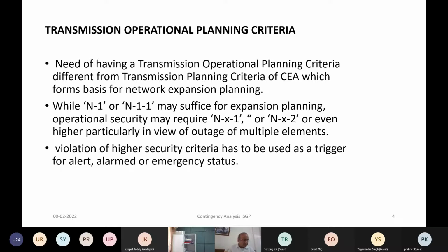Very often, though the planning envisages certain things, in practice the network gets modified because of unforeseen loads being fed or unforeseen conditions of load drawal. We very often hear in terms of grid discipline that a certain region has overdrawn as compared to the schedule. It happens in catering to, say, agricultural load or due to some environmental condition. Suddenly one region may start drawing more power than what it is scheduled. So in such contingencies, certain measures need to be triggered automatically.